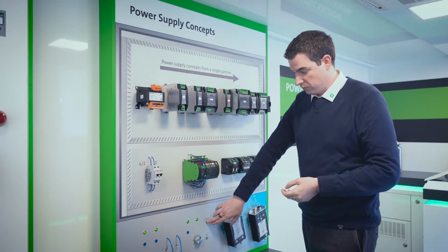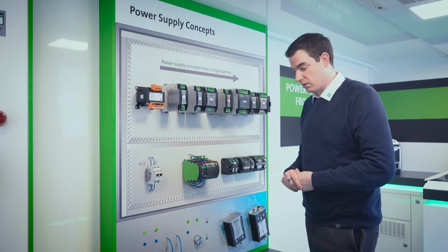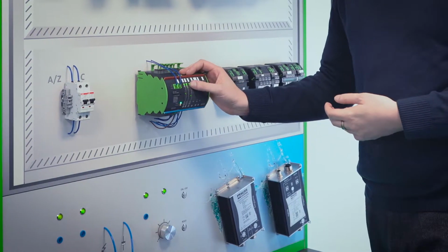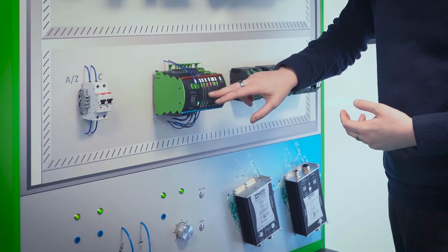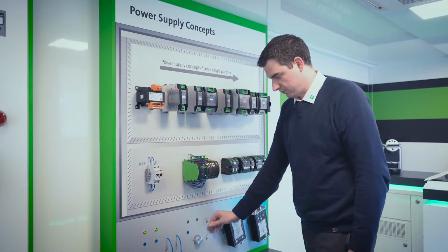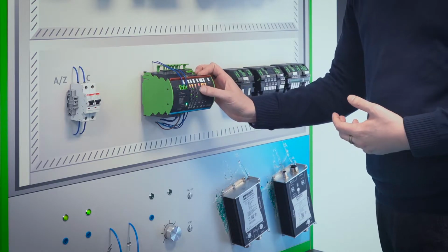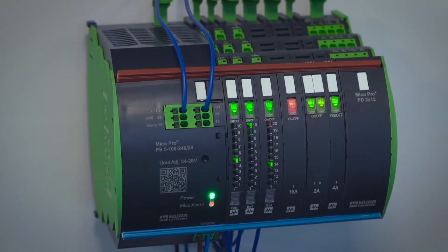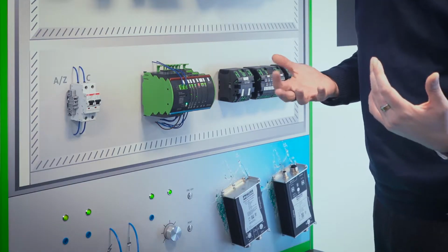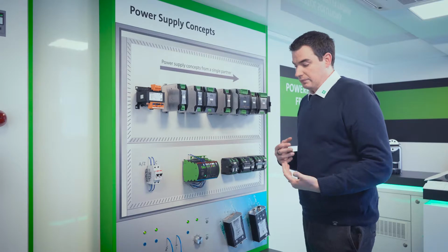So with the global system you are able to disable and enable the entire system as a whole. What it doesn't do, for safety purposes, is modify anything that's been hard turned off. So as we turn off modules, those two turned off there see red. And then remotely turn the system on and off, it doesn't change the state of that module there. As we turn it back on, the module stays disabled. That's for safety purposes in case someone's doing maintenance on parts of the system, or they've consciously turned that off because there isn't anything connected to the other end.